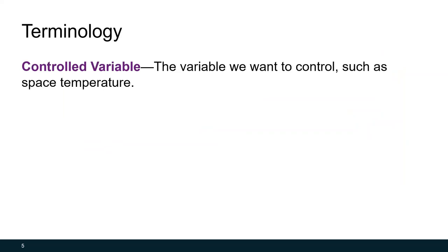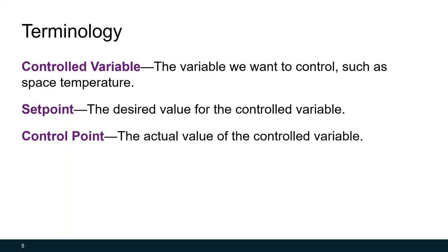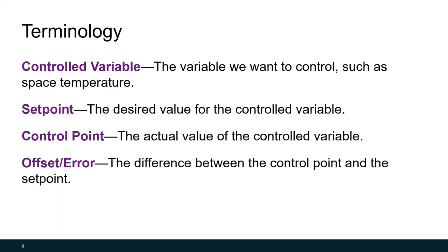Throughout this video we'll be using some terminology that is important to understand. The first term is the controlled variable — the variable we want to control. An example is a home thermostat where we're trying to control space temperature. What we set our thermostat to is called the set point, which is the desired value for the controlled variable. What the temperature in your house actually is is the control point — the actual value of the controlled variable at a given time. The difference between the two is called the offset or the error; they are interchangeable terms.